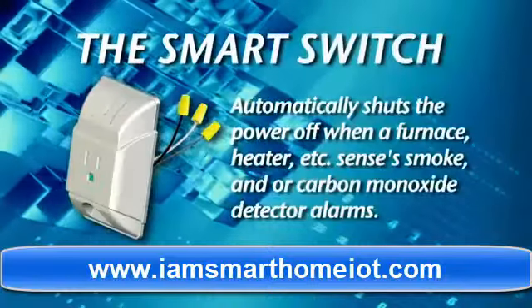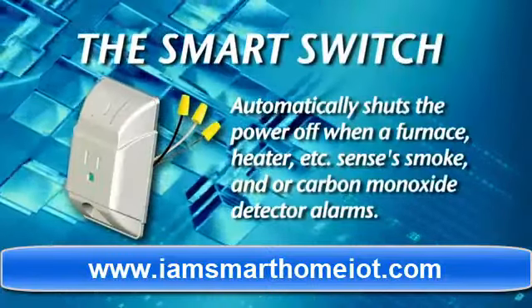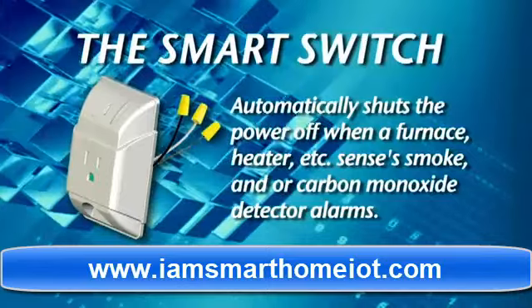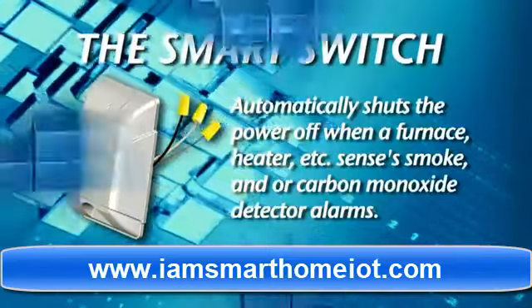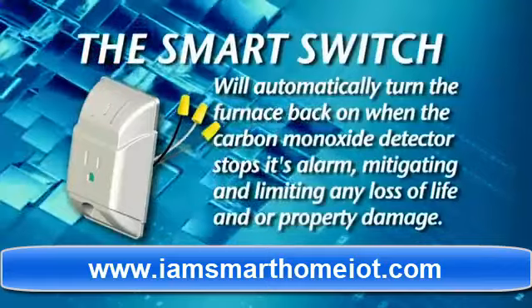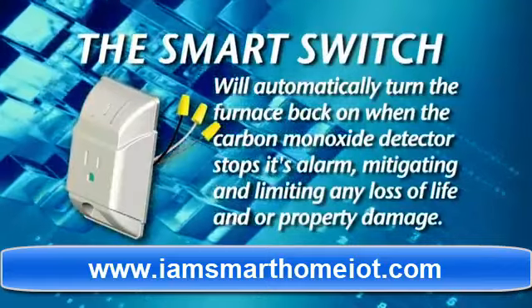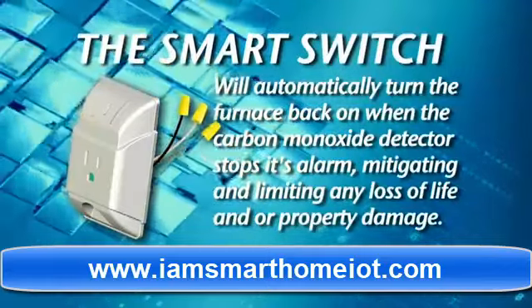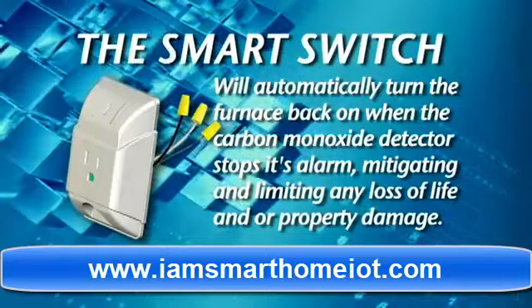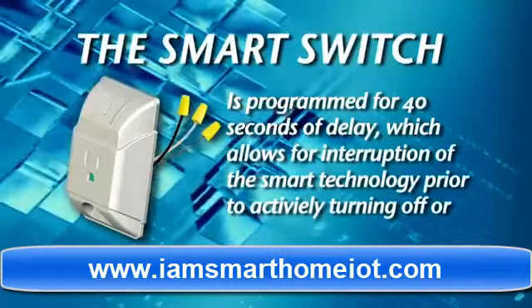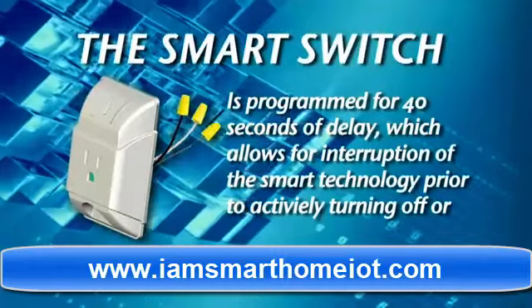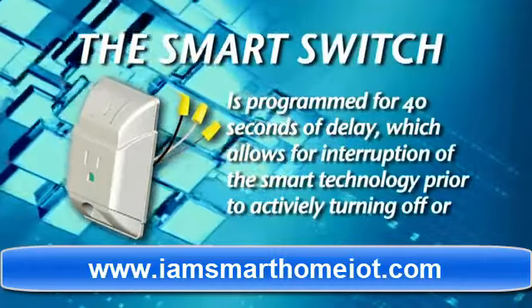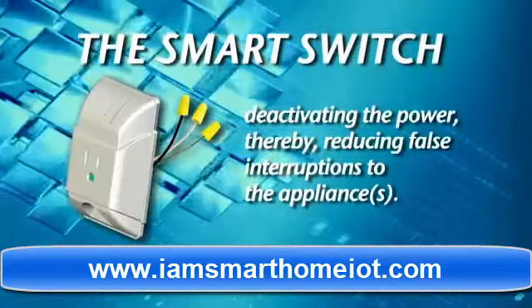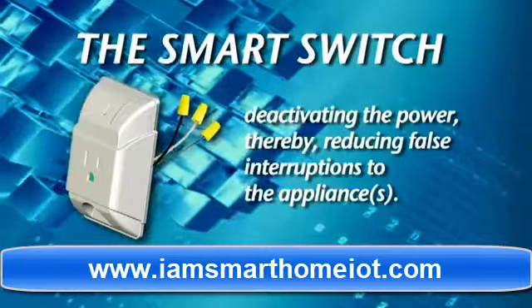The smart switch will automatically shut the power off when a furnace, heater, etc. senses a smoke and/or carbon monoxide detector alarm. The smart switch will automatically turn the furnace back on when the carbon monoxide detector stops its alarm, mitigating and limiting any loss of life and/or property damage. The smart switch is programmed for 40 seconds of delay, which allows for the interruption of the smart technology prior to actively turning off or deactivating the power, thereby reducing false interruptions to the appliance.